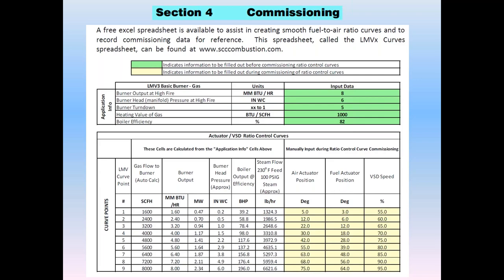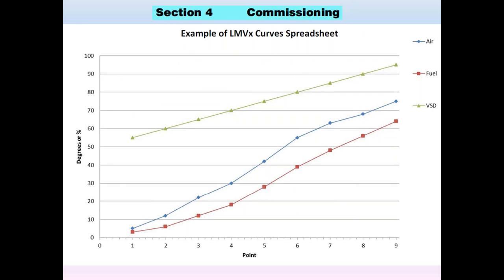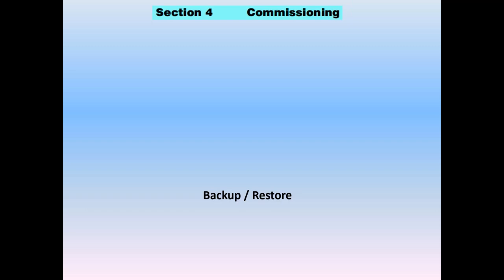There's a free Excel spreadsheet on the website that helps you put in fuel values such as clocking your meters, documenting your fuel, air, and VSD positions. It gives you an idea of burner head pressures to expect, resulting boiler horsepower, steam flow, output in megawatts or millions of BTUs, and cubic feet of gas if you clock your meter. It's a very convenient and nice documentation of your burner curve.